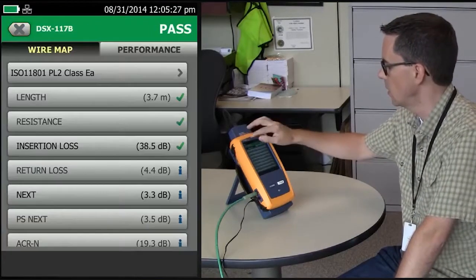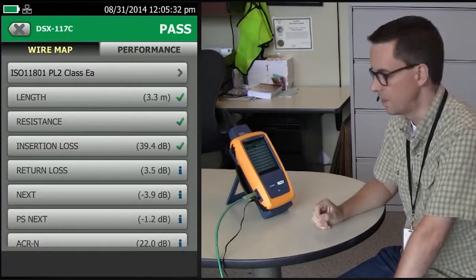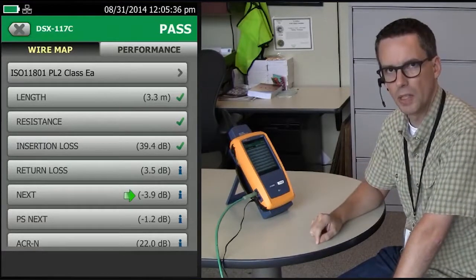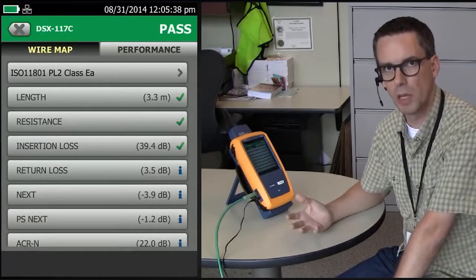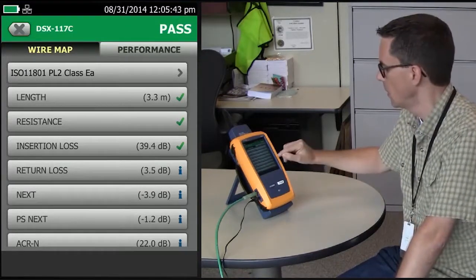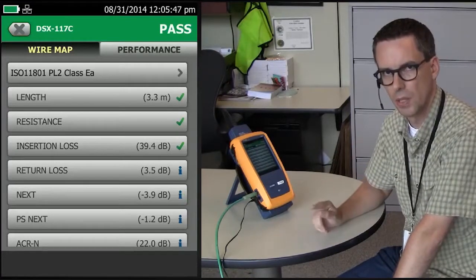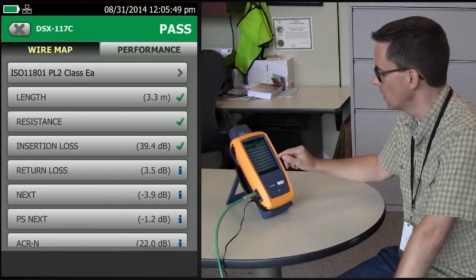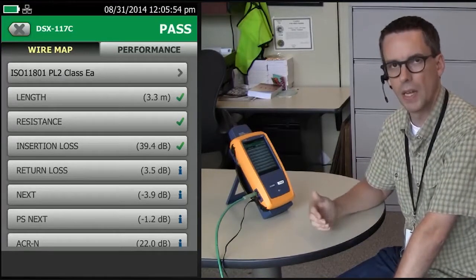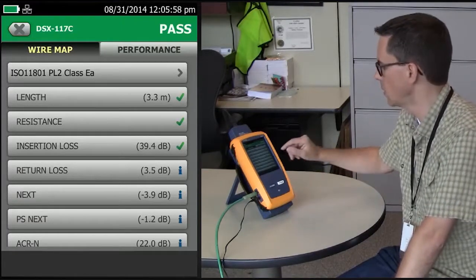Now there is another interesting quirk. Let's look at this result here. The margin is minus 3.9 dB for near-end crosstalk, so that should be a fail, correct? Because minus is below the test limit. But the DSX is showing an eye next to it, not an X. Why? Because the insertion loss on this particular link, quite short at 3.3 meters, never actually reached 4 dB.